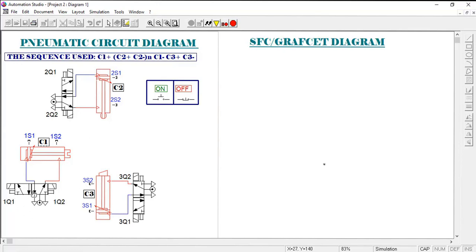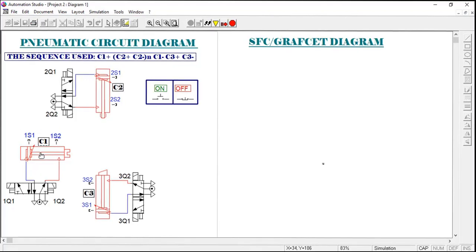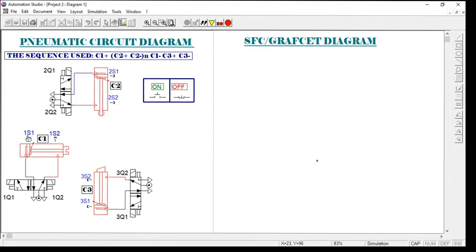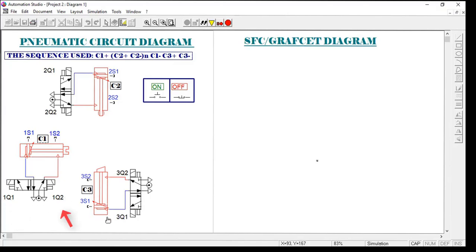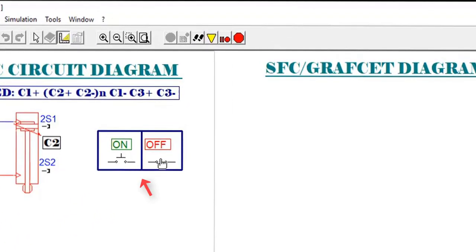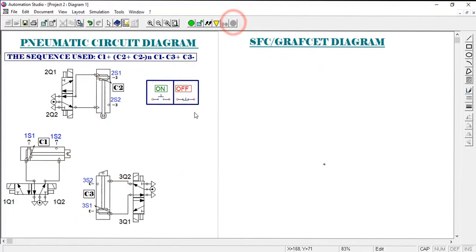Each cylinder also has sensors. On a double-acting cylinder, 1S1 refers to the first sensor on the first cylinder, and 1S2 is the second sensor on the first cylinder, and so on. For solenoids, we have 1Q1 and 1Q2 for the first cylinder, and 2Q1 and 2Q2 for the second — used to turn the solenoids on and off.